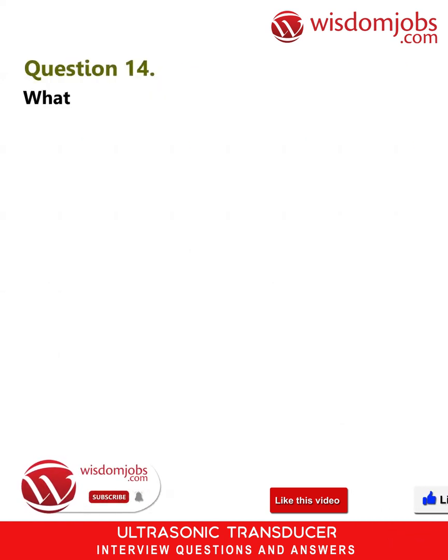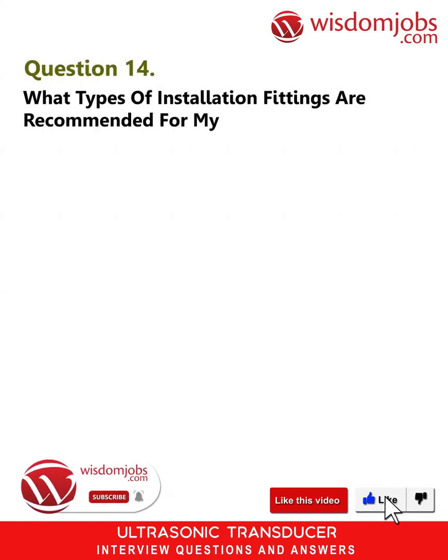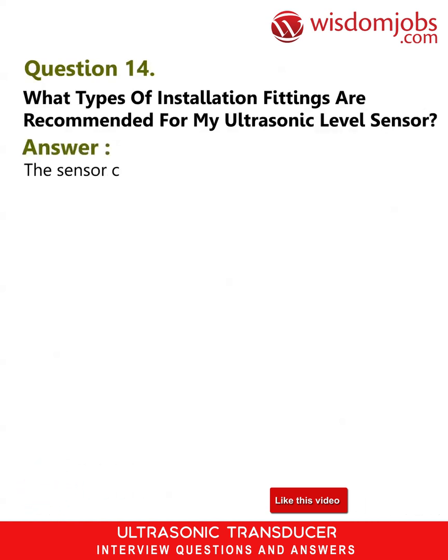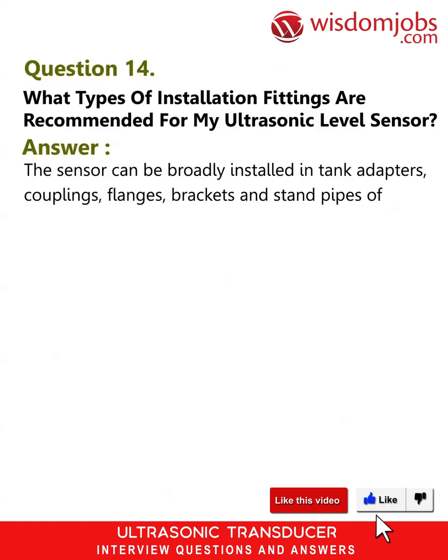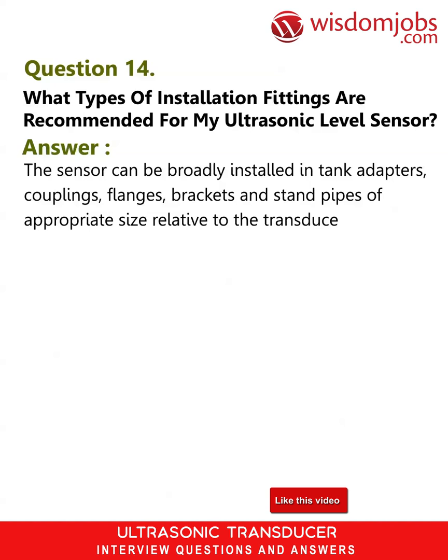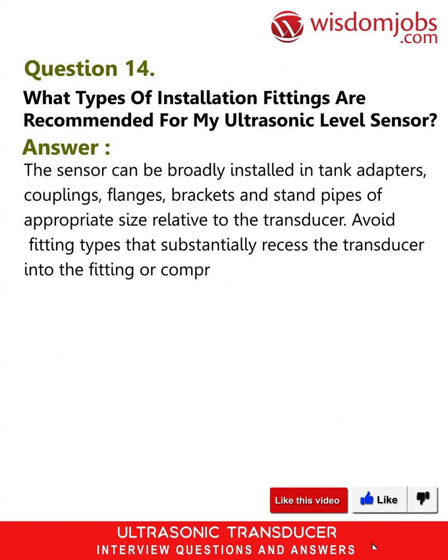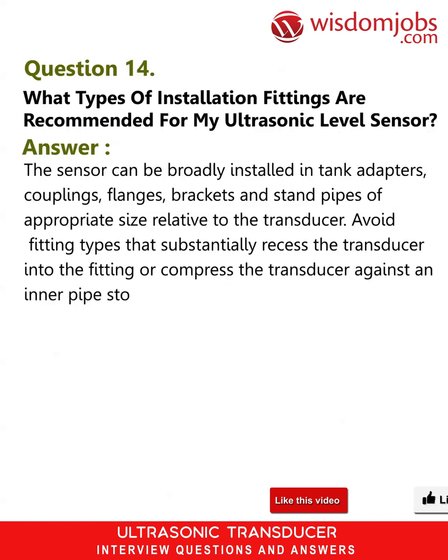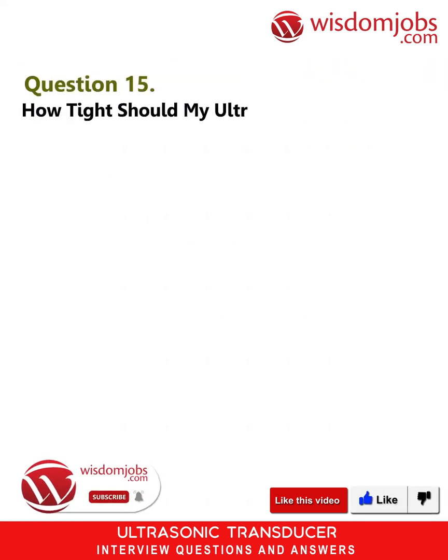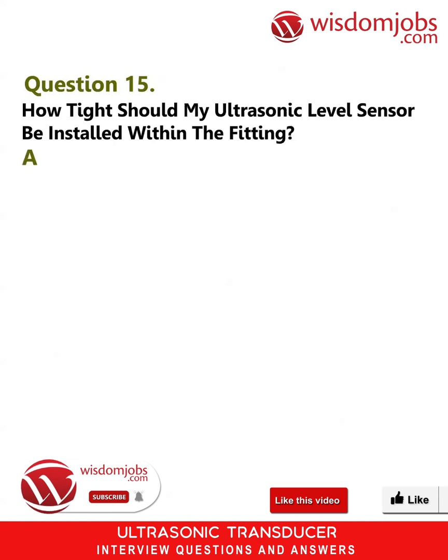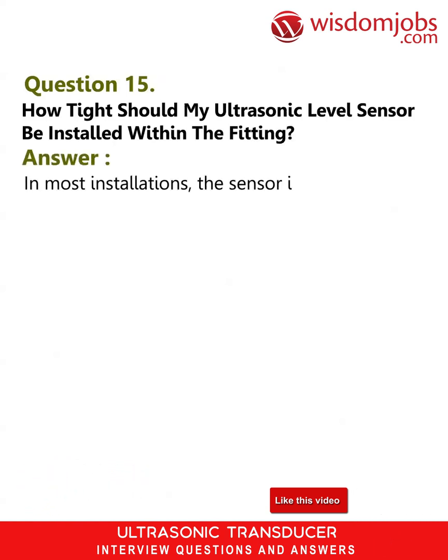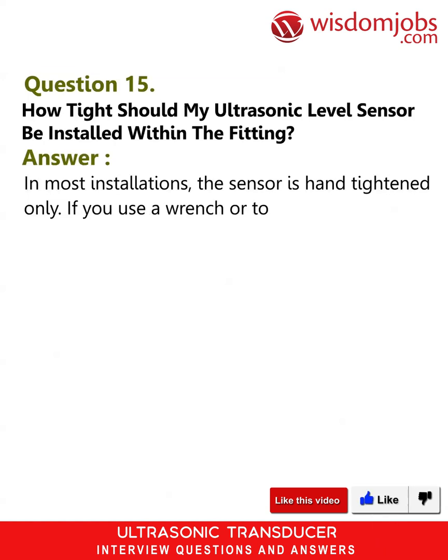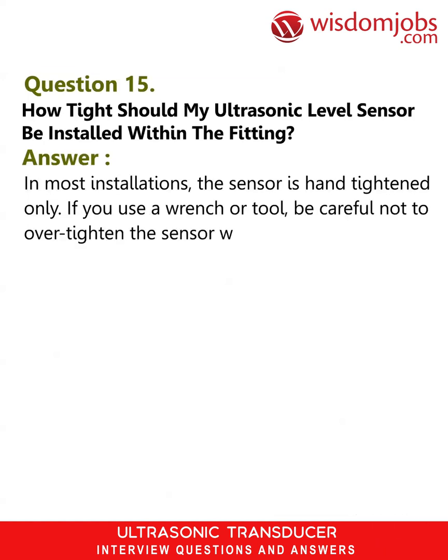Question 14. What types of installation fittings are recommended for my ultrasonic level sensor? Answer. The sensor can be broadly installed in tank adapters, couplings, flanges, brackets, and standpipes of appropriate size relative to the transducer. Avoid fitting types that substantially recess the transducer into the fitting or compress the transducer against an inner pipe stop. Use plastic fittings whenever possible. Question 15. How tight should my ultrasonic level sensor be installed within the fitting? Answer. In most installations, the sensor is hand-tightened only. If you use a wrench or tool, be careful not to over-tighten the sensor within the fitting.